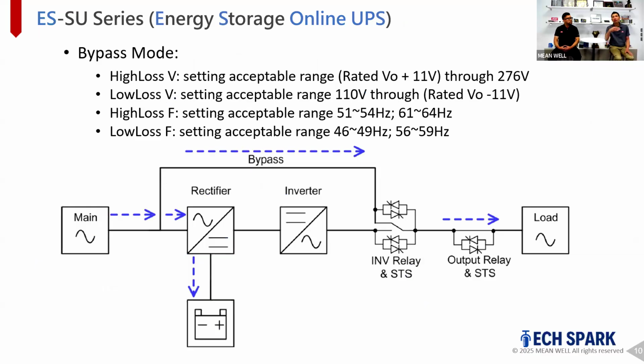You see earlier like double converter, it has the main on the left, a rectifier and an inverter. That's why you call it double converter or online UPS. It has the A to D and D to A, and also a battery, then goes to the load. Under bypass mode, you see how the power flows in the blue line: AC in, charges the battery, then bypasses both rectifier and inverter and goes directly to the load. When your AC is out, it's going to go to UPS mode or battery mode.